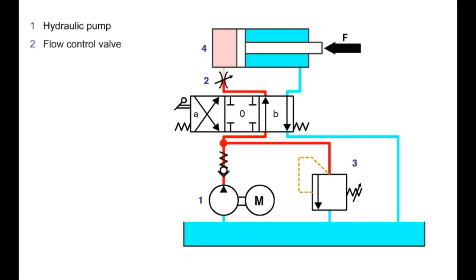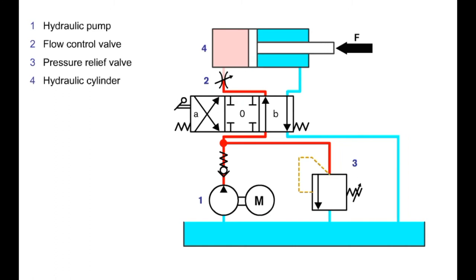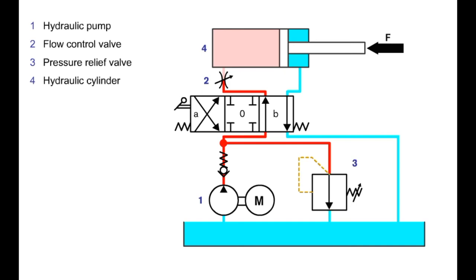The following pressures occur with a flow control valve in a hydraulic system when extending the hydraulic cylinder, depending on the position of the flow control valve. Between the hydraulic pump and the flow control valve, we obtain approximately the pressure regulated by the pressure relief valve as soon as it is opened. Between the flow control valve and the hydraulic cylinder, we obtain an approximate pressure which corresponds to load F.